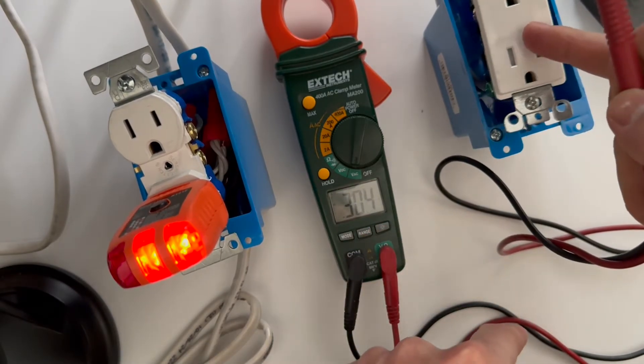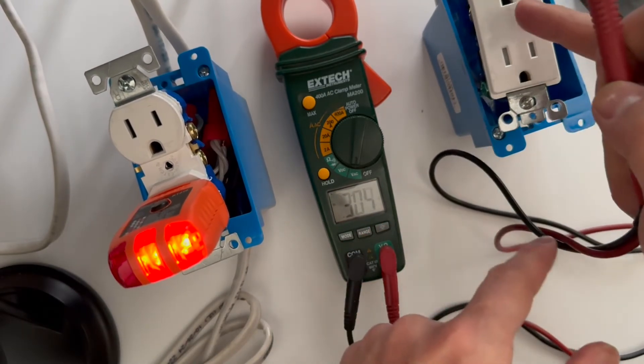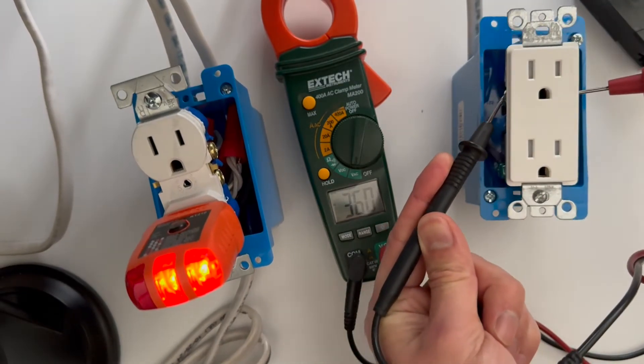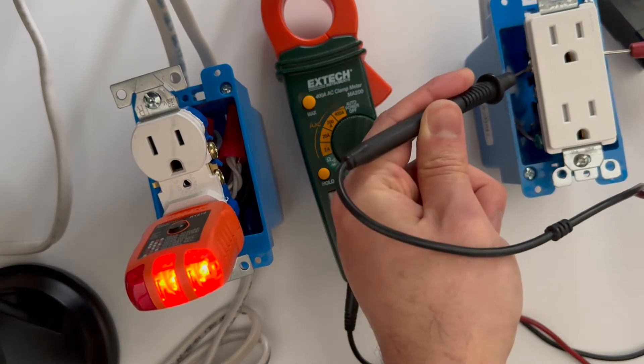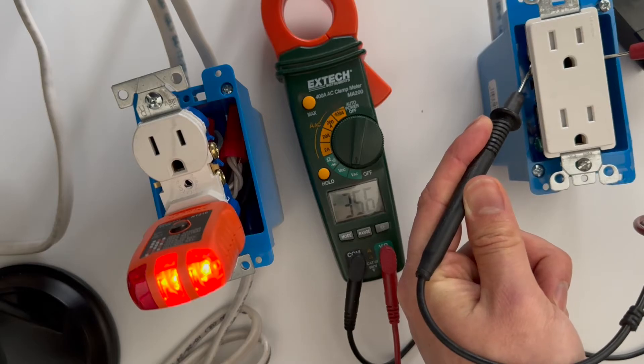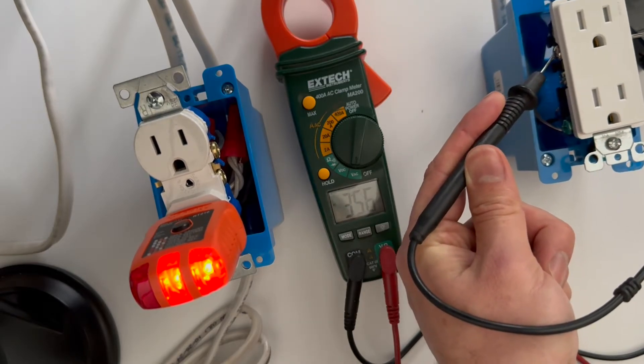In an outlet that you don't have power but you have hot ground reversed, when you try to read between neutral and the hot, it's showing 35 volts. That's an open neutral.